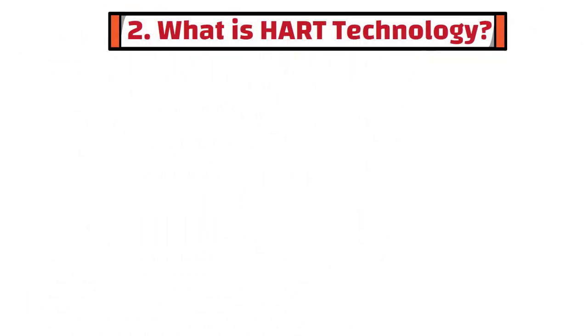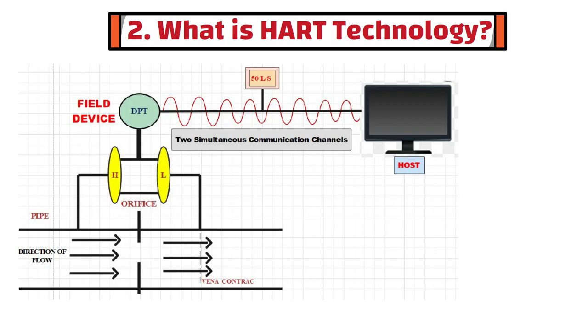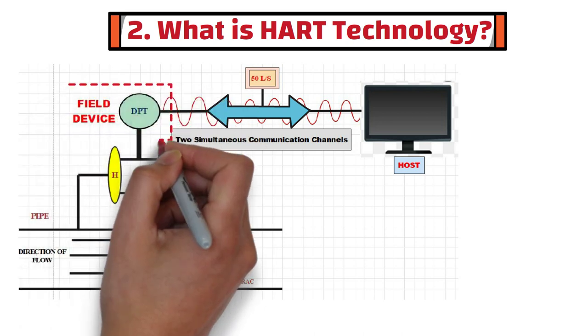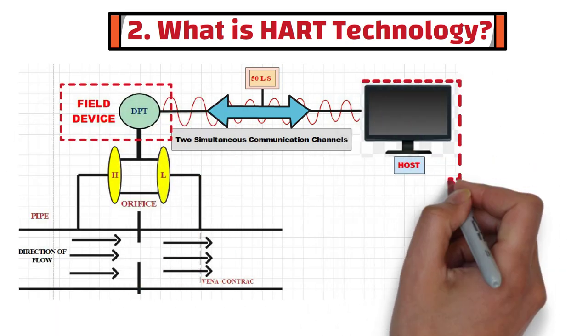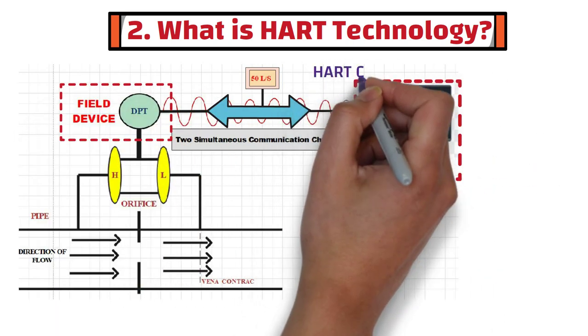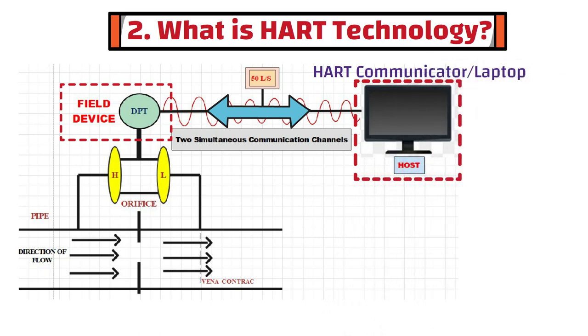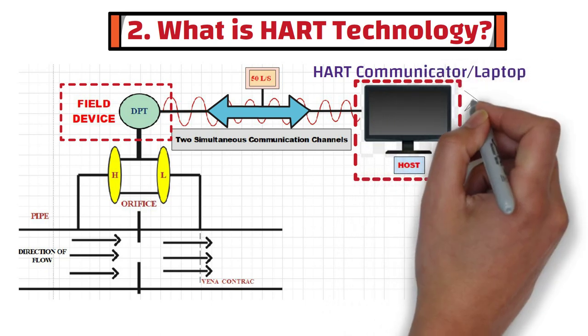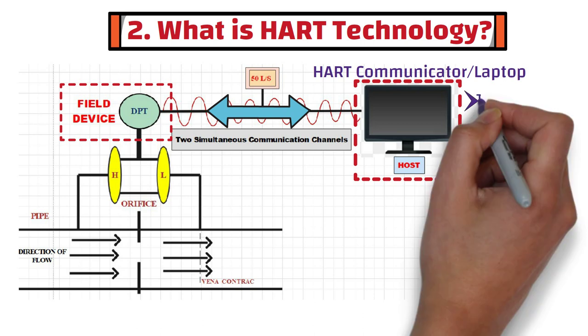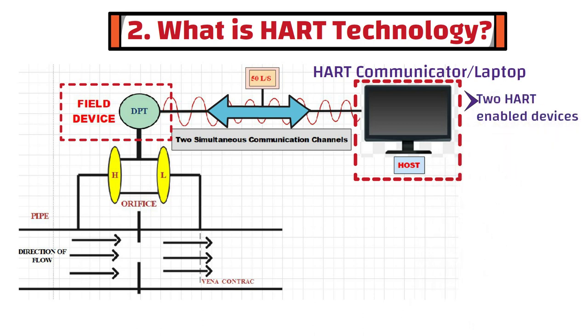Second question is, what is the HART technology? HART is a bi-directional communication protocol which provides data access between intelligent field instruments and host systems. The host can be HART communicator or laptop. In addition to this, HART communication can occur between two HART-enabled devices. For example, it can occur between a smart field device and a control or monitoring system.